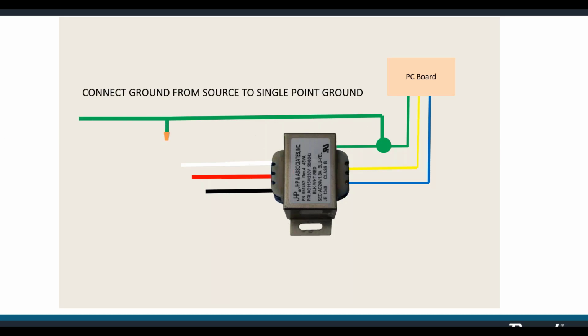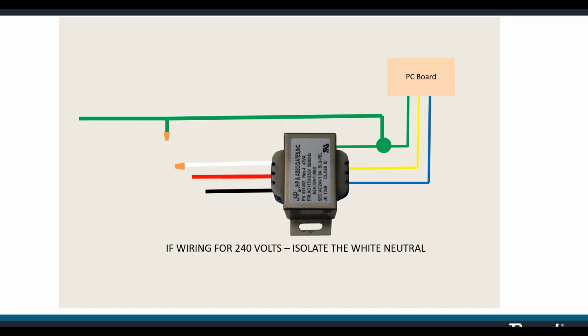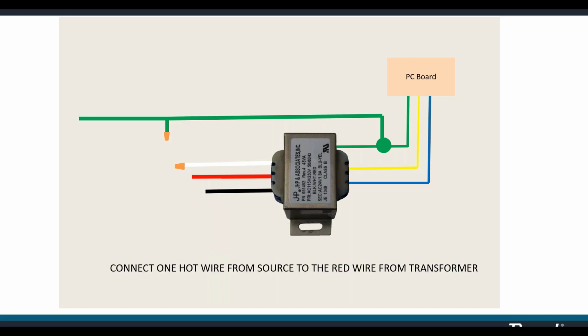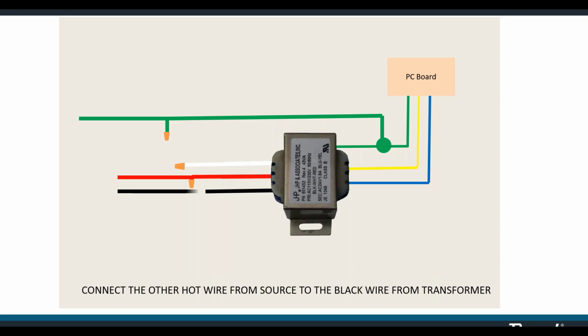All right. If you're wiring 240, we don't need the white wire. White wire is a neutral. We don't need that on a 240 line, so we're going to go ahead and cap that off. Your remaining 2 wires are your hots. So you've got 2 wires coming out of the transformer and 2 wires coming out of the conduit. One of those hot wires goes to the red. The other one goes to the black.